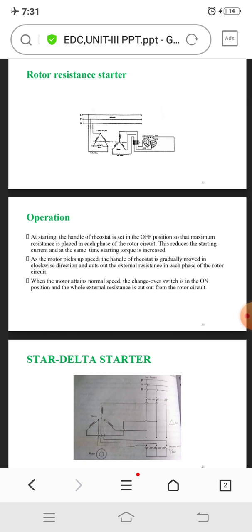This reduces the starting current and at the same time starting torque is increased. As the motor picks up speed, the handle of the rheostat is gradually moved in a clockwise direction and cuts out the external resistance in each phase of the rotor side. When the motor attains normal speed, the changeover switch is in the on position and the whole external resistance is cut out from the rotor circuit.